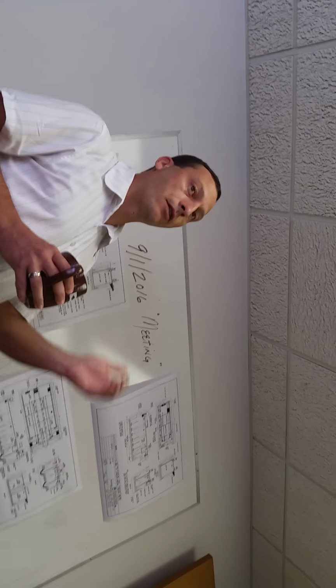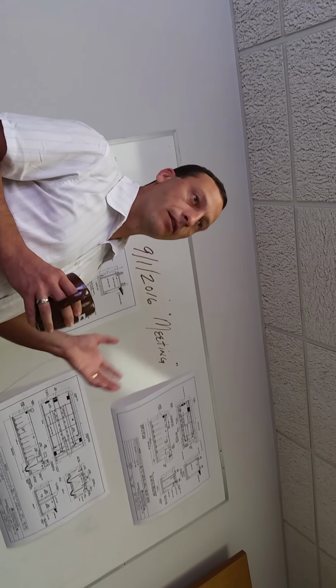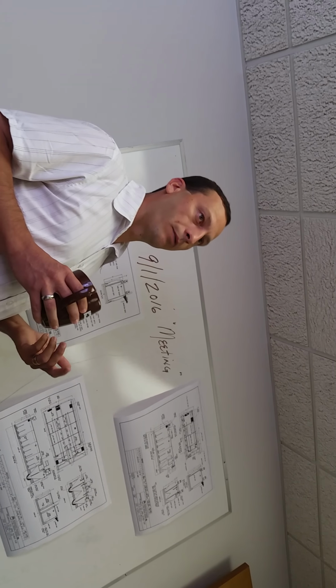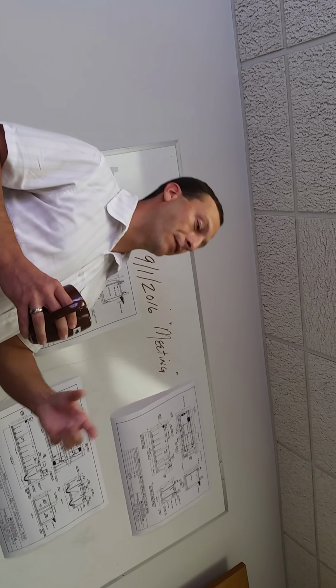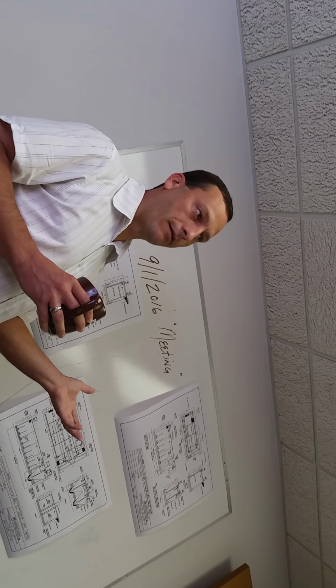The only thing I would say as far as heavy metals for us is on an industrial application. There are certain levels of those heavy metals that Paul and I have to look out for that may kill or inhibit biological activity. So when we're looking into an industrial, we have to get some really good numbers off of them to say, hey, can you give us a full wastewater panel? Specifically, we're looking for these culprits that might make biological treatment damn near impossible.